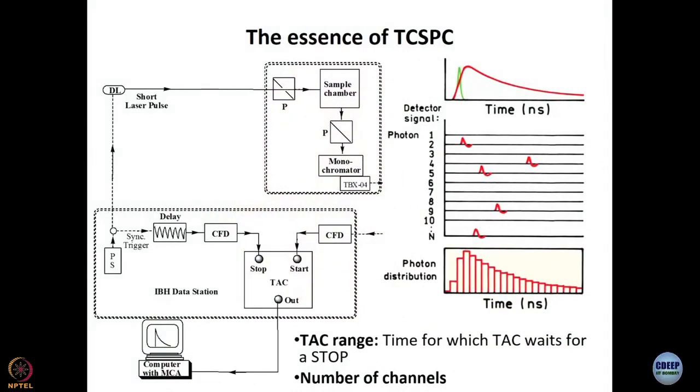The second important term is number of channels. TAC range is associated with the TAC, but number of channels is associated with the multi-channel analyzer (MCA). Suppose you have a 50-nanosecond TAC range and 1000 channels — then each channel represents 50 picoseconds. That is the time resolution. If instead you have 10,000 channels, the resolution becomes 5 picoseconds per channel.